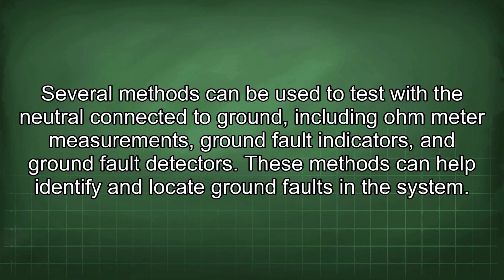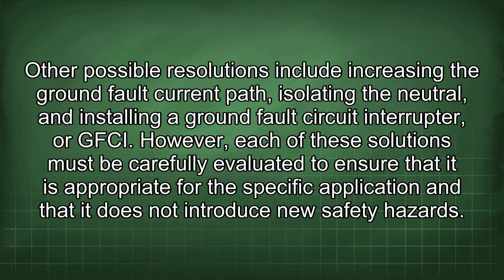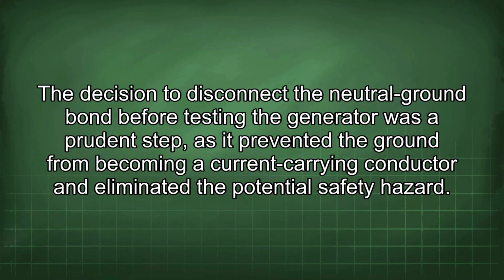Several methods can be used to test with the neutral connected to ground, including ohmmeter measurements, ground fault indicators, and ground fault detectors. These methods can help identify and locate ground faults in the system. Other possible resolutions include increasing the ground fault current path, isolating the neutral, and installing a ground fault circuit interrupter, or GFCI. However, each of these solutions must be carefully evaluated to ensure that it is appropriate for the specific application and that it does not introduce new safety hazards. The decision to disconnect the neutral ground bond before testing the generator was a prudent step, as it prevented the ground from becoming a current-carrying conductor and eliminated the potential safety hazard.